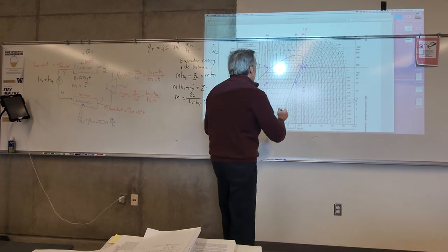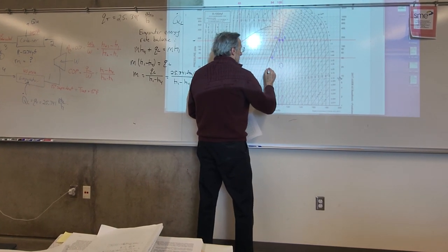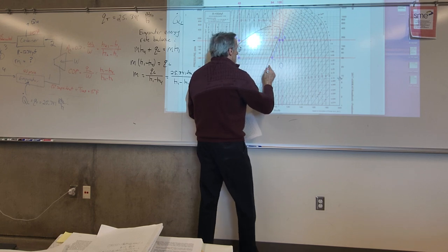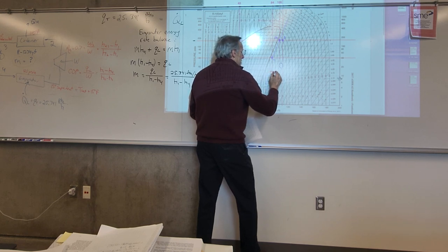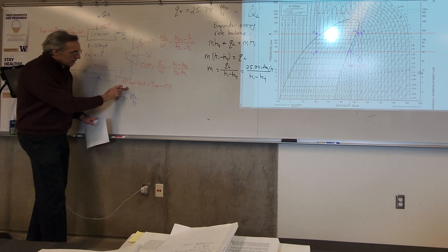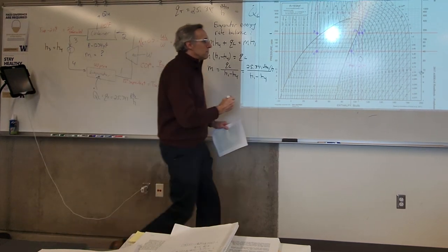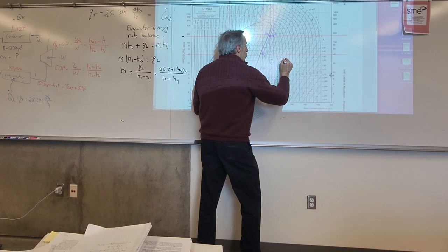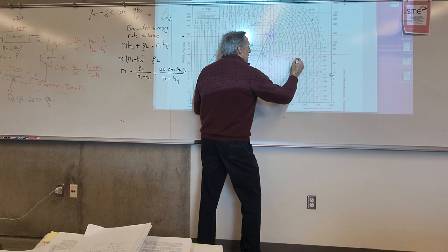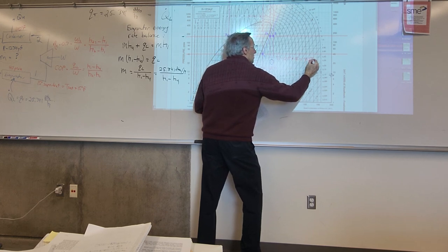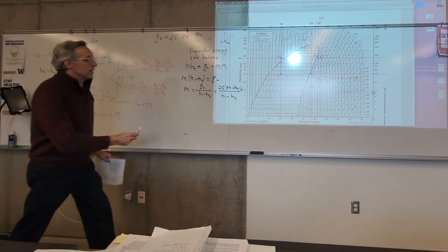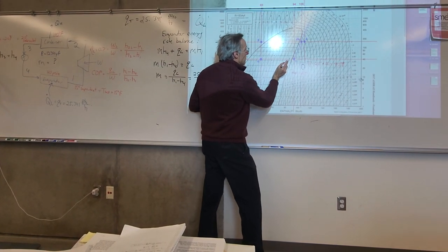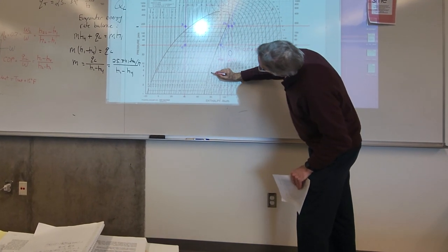and it's 25 degrees Fahrenheit. So that's going to be my T-sat at one. This is the temperature in the evaporator, 25 degrees. And my design state specification is that I come out with 15 degrees of superheat. So that means T1 is going to be 25 degrees plus 15 equals 40 degrees F. That's my 15 degrees of superheat. So I'm at 25 degrees there, and I add 15 to get to 40. Here's 40 degrees.